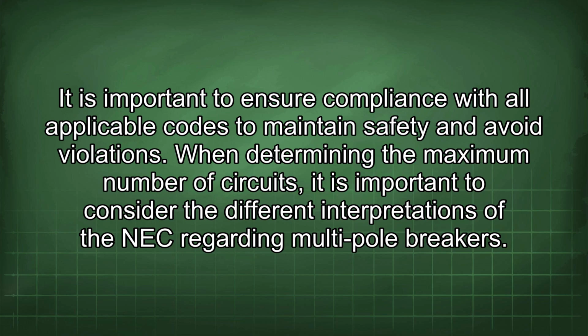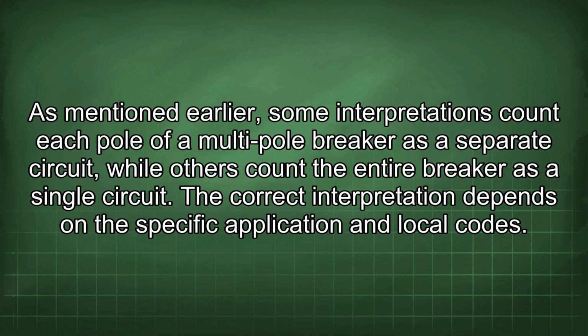When determining the maximum number of circuits, it is important to consider the different interpretations of the NEC regarding multi-pole breakers. As mentioned earlier, some interpretations count each pole of a multi-pole breaker as a separate circuit, while others count the entire breaker as a single circuit. The correct interpretation depends on the specific application and local code.